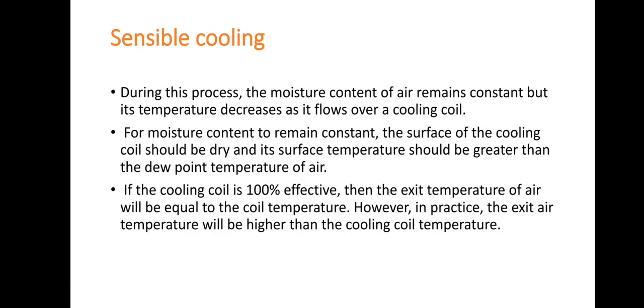Sensible cooling is the process in which the moisture content of the moist air remains constant and its temperature decreases as it flows through the cooling coil. So for the moisture content to remain constant, the surface of the cooling coil should be dry and its surface temperature should be greater than the dew point temperature of air.